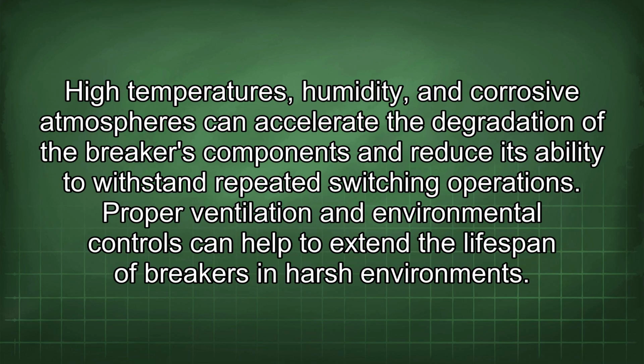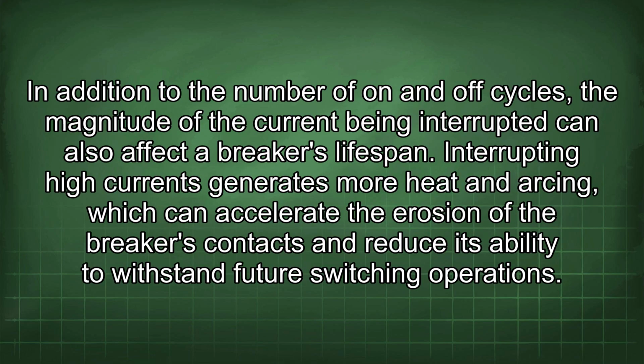High temperatures, humidity, and corrosive atmospheres can accelerate the degradation of the breaker's components and reduce its ability to withstand repeated switching operations. Proper ventilation and environmental controls can help to extend the lifespan of breakers in harsh environments. In addition to the number of on and off cycles, the magnitude of the current being interrupted can also affect the breaker's lifespan. Interrupting high currents generates more heat and arcing, which can accelerate the erosion of the breaker's contacts and reduce its ability to withstand future switching operations.